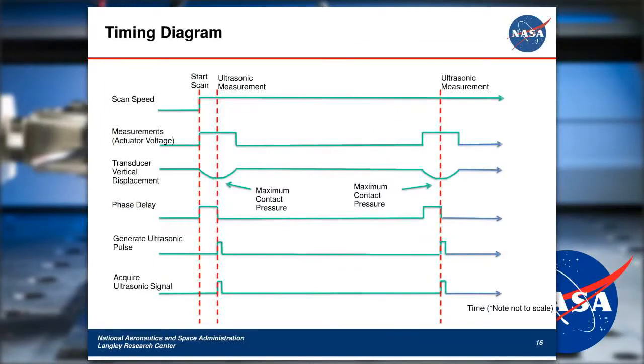So here's the timing diagram. If you'll look at the second waveform from the top, we have the actuator voltage. So that actuator voltage is supplied to the coil, the linear voice coil motor, and that coil then, with the magnet in the center of the coil, causes the vertical displacement. And since you're controlling the transducer assembly electromechanically, there's going to be some delay in moving that mass down. So there's going to be a delay when you get the maximum contact pressure from when you apply the actuator voltage. And so we introduce a phase delay. So we're synchronizing the firing of the ultrasonic pulse and the acquisition of the ultrasonic pulse to that phase delay when we get maximum contact pressure. And we've measured it to be about 2 milliseconds.